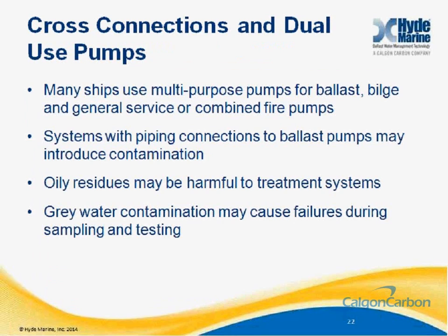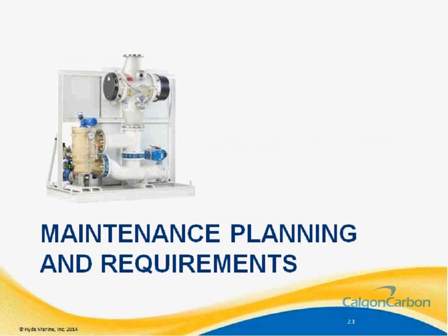Finally, it is important to remember that ballast piping systems are not standalone systems. Most ballast piping systems can be cross-connected with numerous different piping systems on the ship. When ballasting, particularly when doing compliance testing, it is important to make sure that the lines are flushed from any bilge, fire water, gray water, or general service applications that the piping may have been used for that may contaminate the samples which supposedly have been taken from the ballast system. Careful consideration of the cross-connections of piping systems will go a long way to ensuring success when you face field testing in the future.